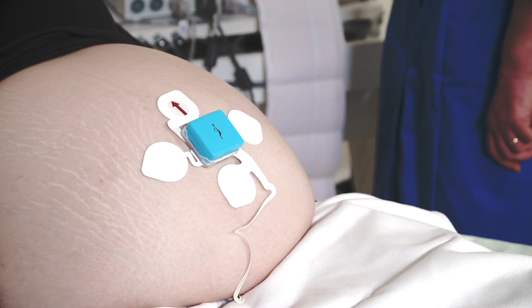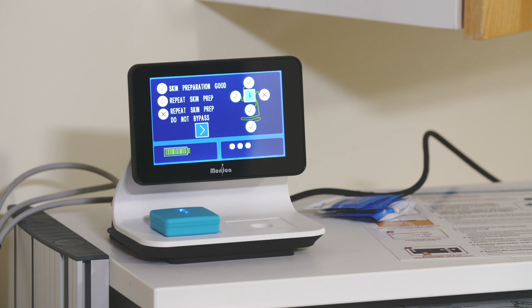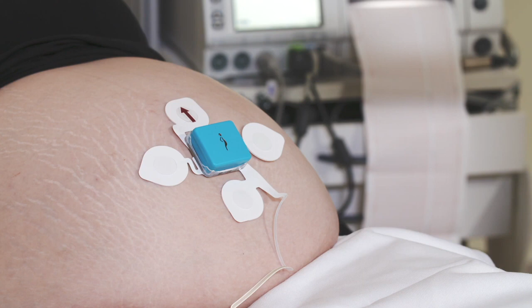Training Session 4. What to do when the skin prep fails. You have done the skin prep as directed, and yet the skin electrode check screen is showing that one or more of the electrodes has not passed the skin electrode check, and a red cross or orange O is being displayed. You should not bypass a red cross if it can be avoided, so peel back the problem electrode and wipe the skin dry to remove any excess electrode gel.